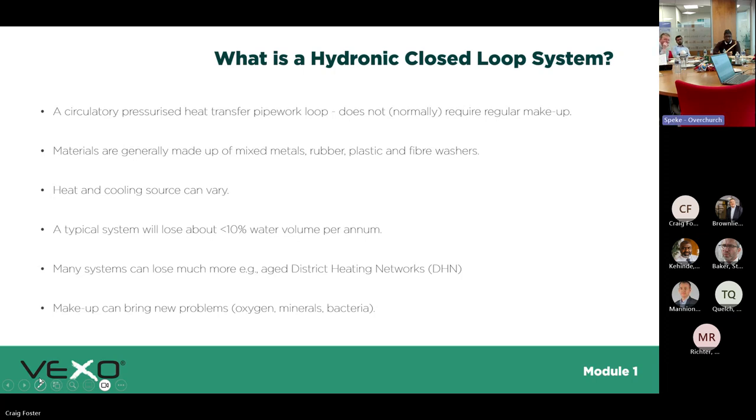You'll all know what a hydronic closed-loop system is — it's pressurized water within pipework, and you generally get some form of losses depending on the application. District heat networks lose more, but you generally lose about 10 percent. The reason we focus on water loss in this CPD is it's not just about the water in the system — it's how you're feeding water back in. If you're putting mains water back in via the pressurization unit that's untreated, or you've got a leak, you could be inducing oxygen or other harmful elements into an already clean system.